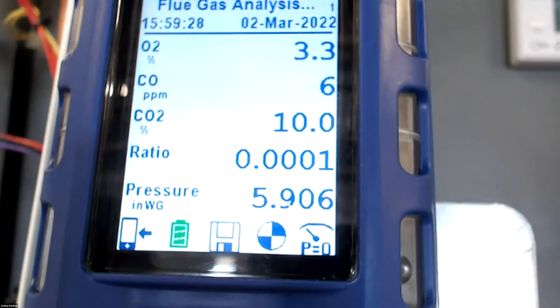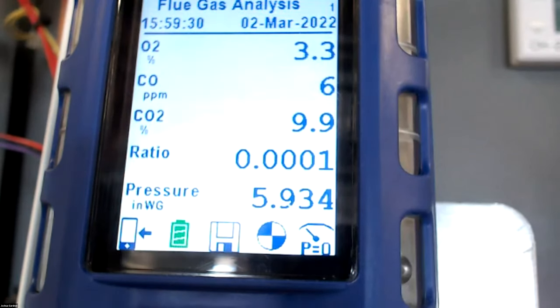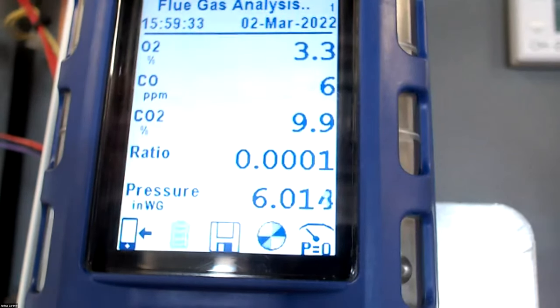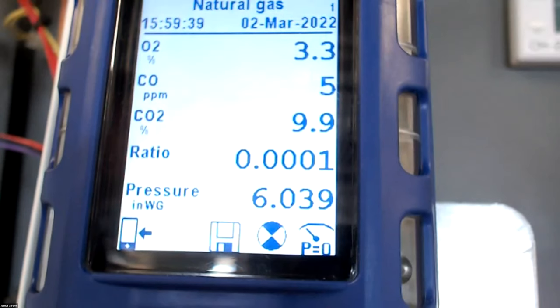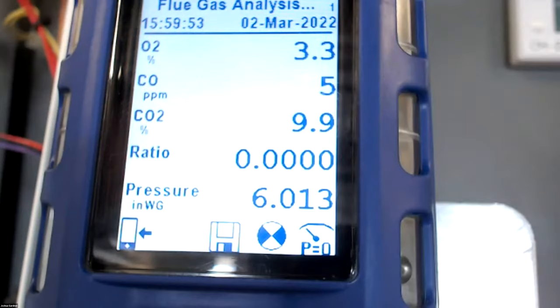Well, that tells me I don't have enough pressure coming through my gas valve. This is where we do our offset adjustment, okay? And the offset adjustment is only done in low fire. We set the offset adjustment, get it within spec, try to hit the target, and then we put it back together, the cap back on there, we bring it to high fire check, and that's it.